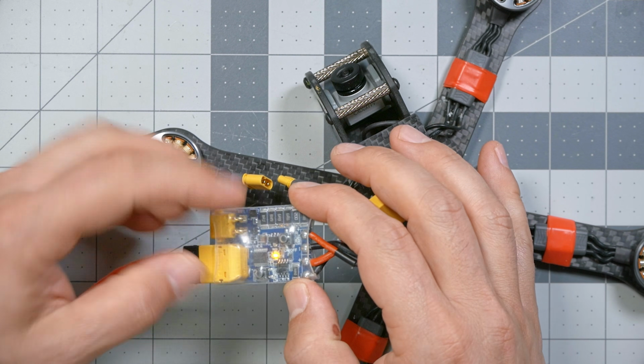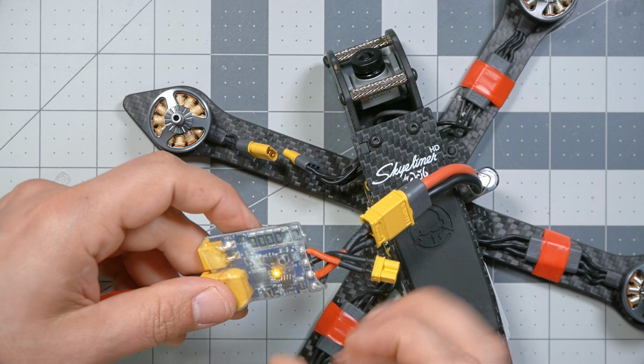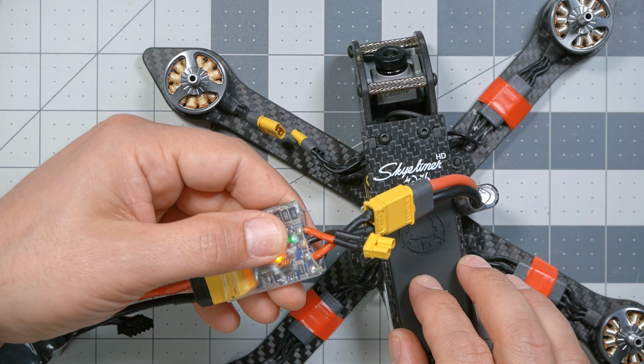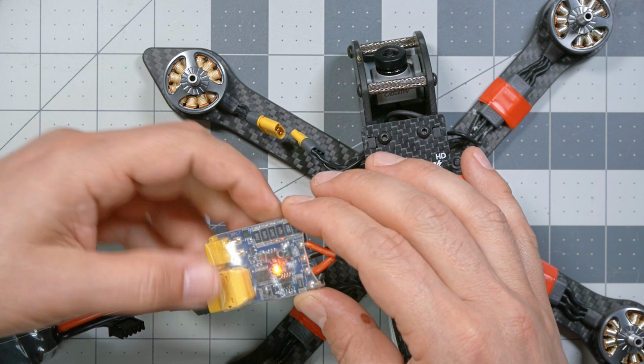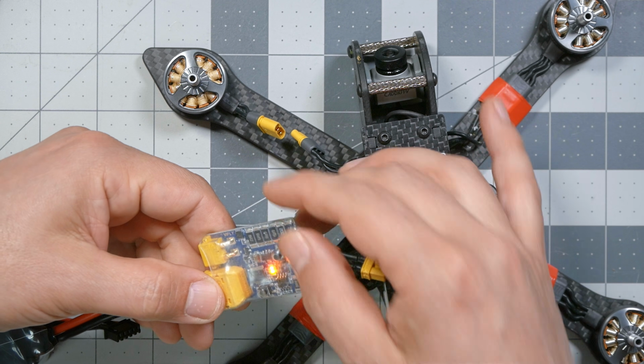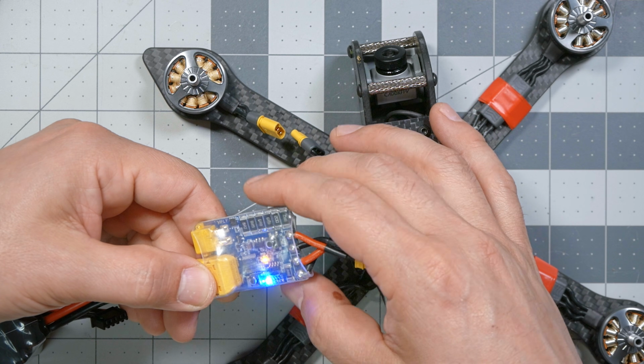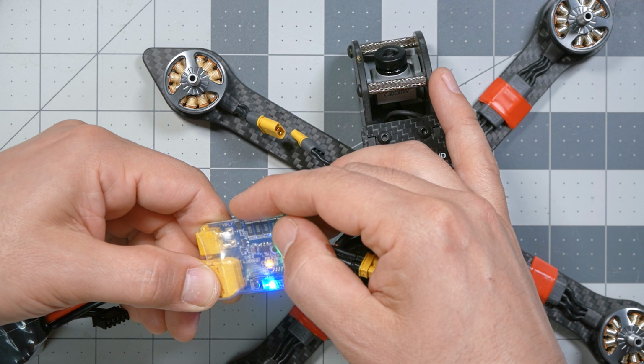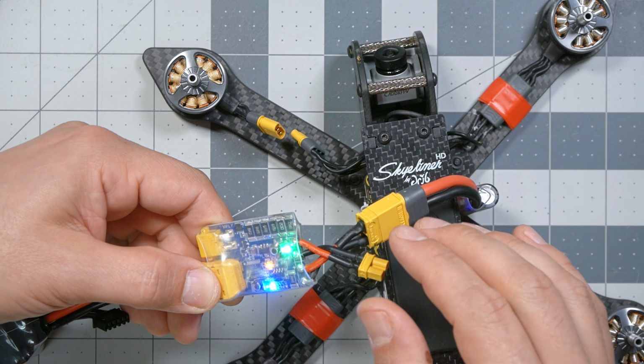So here we are again, we're on 1 amp and we've got the motor unplugged and we're going to try again. Okay, well it started to go, but the 1 amp I think was not enough. So let's go to 2 amps. Okay, perfectly normal. So the smoke stopper tripped when we had the motor connected, but it didn't trip when we disconnected the motor. And that's certainly starting to look like we have a bad motor. Let's talk about motors and how they go bad.